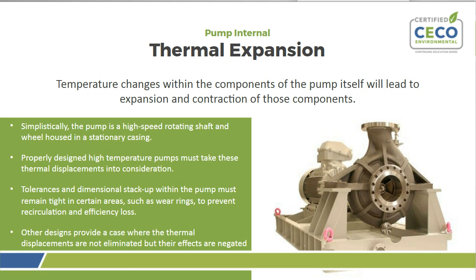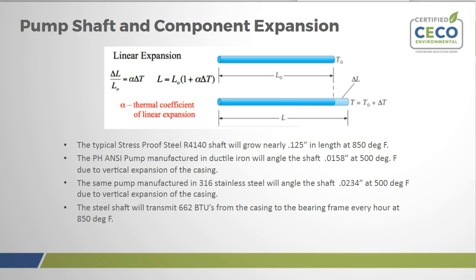For most cases, just a couple examples here. The typical stress-proof steel, which is what is used in a lot of high-temperature shafting and that sort of thing, will grow nearly 1/8 of an inch in length at 850 degrees F. Of course, given that most tolerances within a pump are half thousandths to 10,000ths, that can be somewhat problematic.